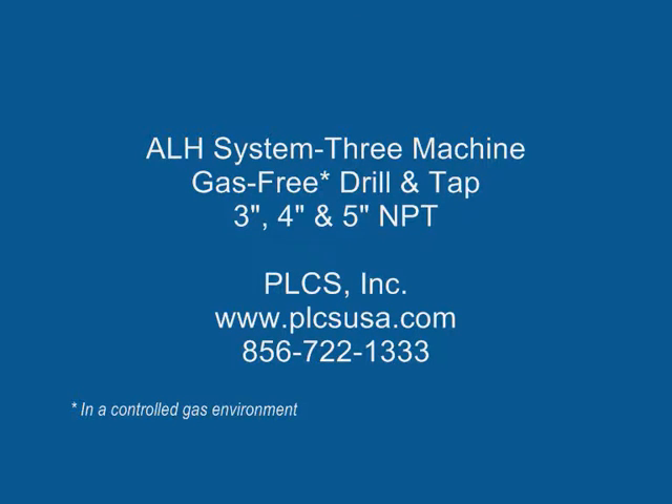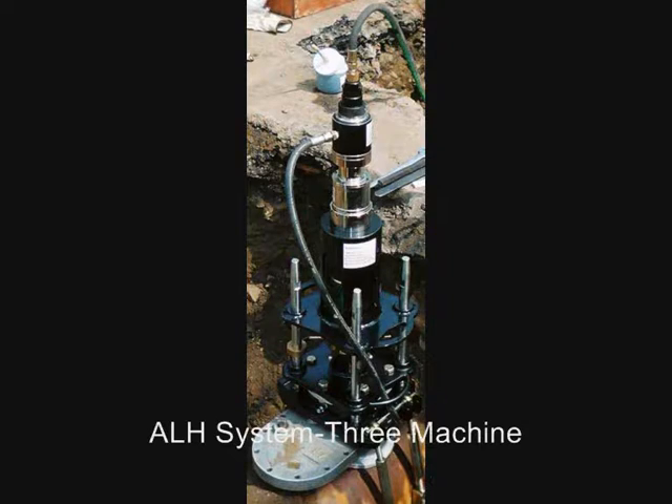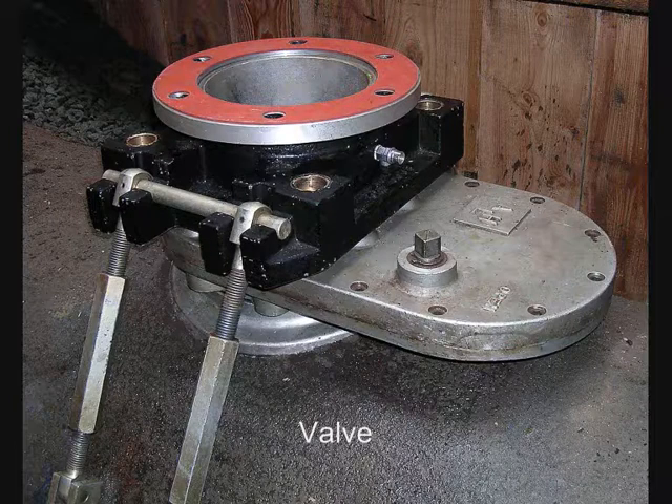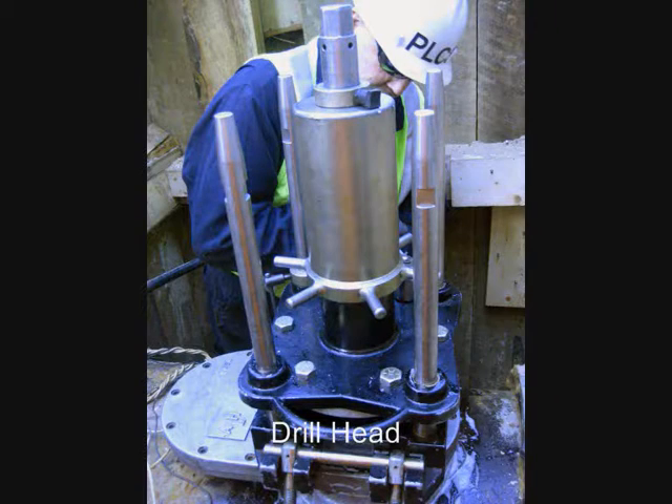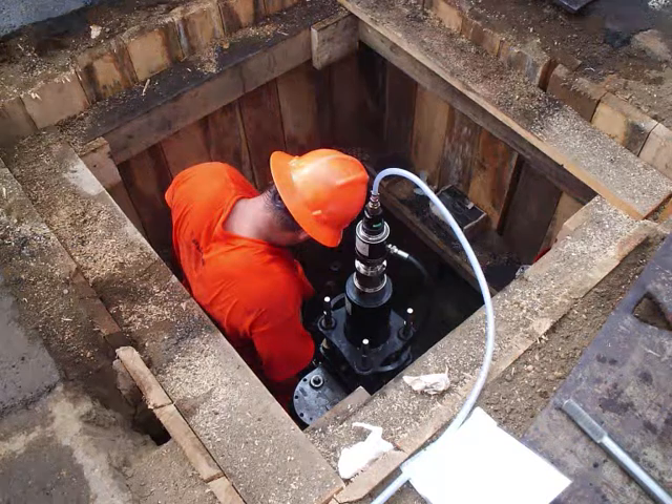The ALH System 3 machine drills and taps 3-inch, 4-inch, or 5-inch NPT threads in steel or cast iron gas mains from 12-inch to 48-inch in diameter at pressures up to 60 PSI under gas-free conditions in under 20 minutes including setup time.